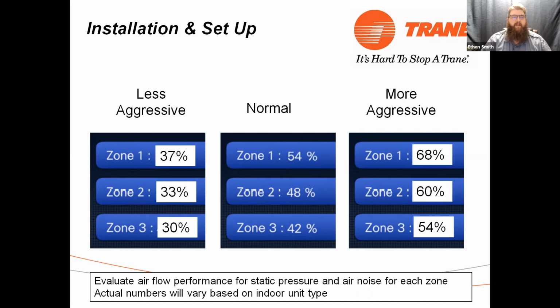So this is just an example of some readings you might get on the same system versus if you're using the less aggressive, normal, or more aggressive set points. Okay, so normally it's going to size my zone 1 to 54% capacity, 48 and 42 for zone 2 and 3. You can see what it does for those same zones in the more aggressive setting.